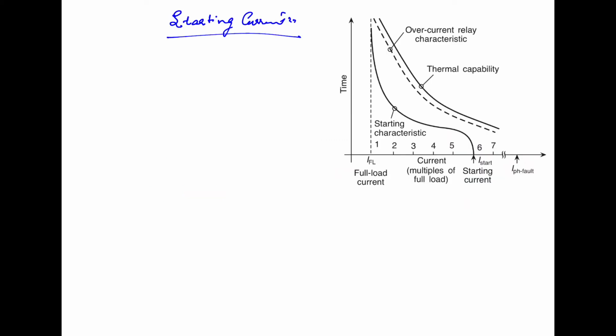Now, one more point: the induction motor draws a very large starting current, of the order of 6 to 8 times the full load current if subjected to direct online starting. The amplitude of the starting current may be comparable to the fault current. Therefore, the overcurrent protection provided to the motor must be able to discriminate between a genuine fault and the overcurrent due to the starting of the motor. So we must have coordination between the starting characteristics of the motor and the overcurrent relay.